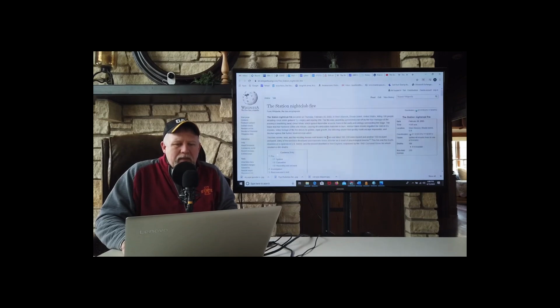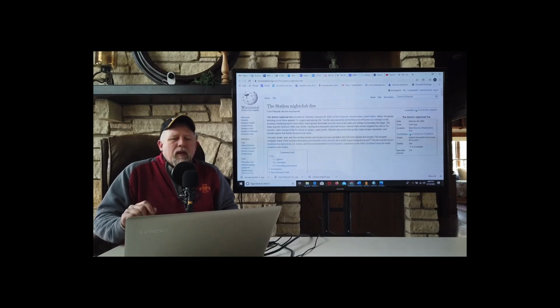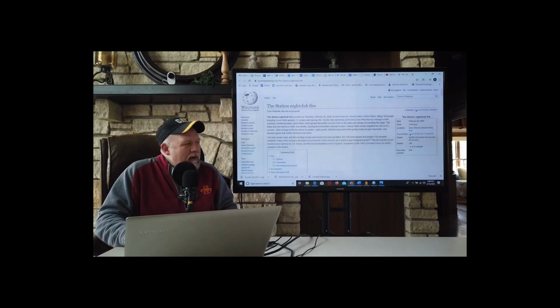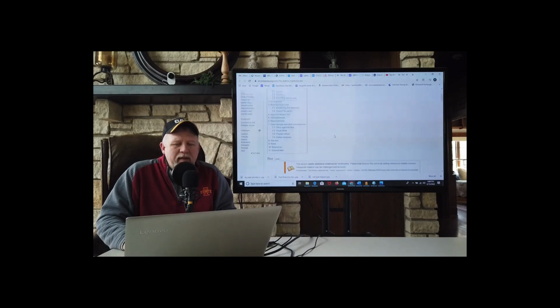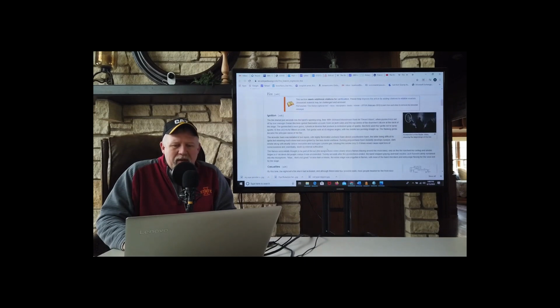What happened? The basics. And we'll see this. The band was playing. Pyrotechnics were set off by the band manager. And apparently, this particular venue had had some complaints of noise in the past. So at some point in the history of the nightclub, they had added a bunch of spray-in foam around the band and stage area to deaden the noise to the outside. Common practice. They also apparently painted that foam black. Some of this was a polyurethane foam. Some of it was a polystyrene foam.